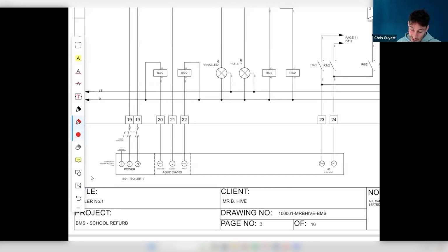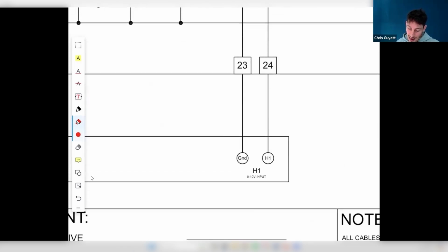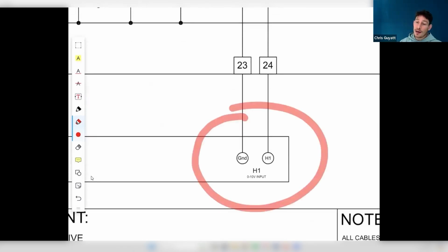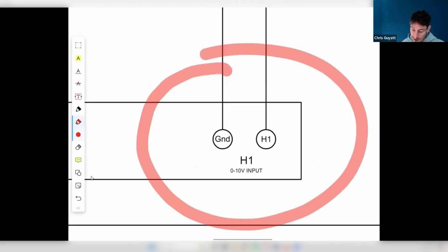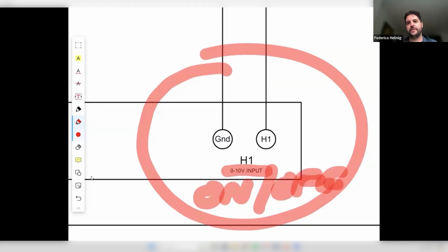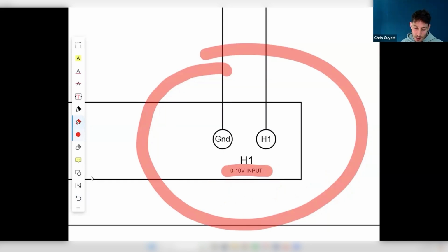Sorry, no - we don't use the additional module for the analog control, that's just for the volt-free and enable output. The boiler natively has that H1 input, and again, looking at the tech manual, it shows that H1 input can be used either for a 0 to 10 volt control signal, or just as an on-off signal. So to answer your question, it's in the spec and in the tech manual.